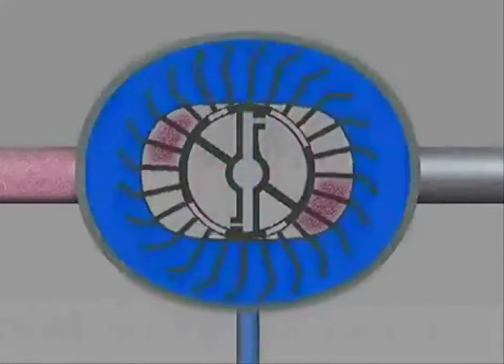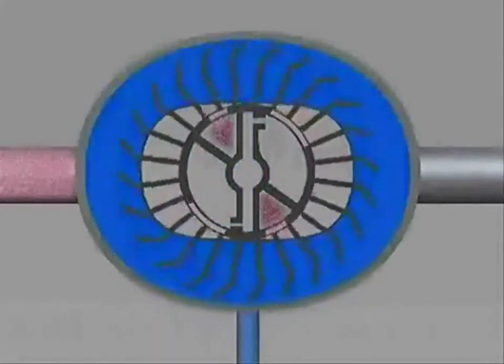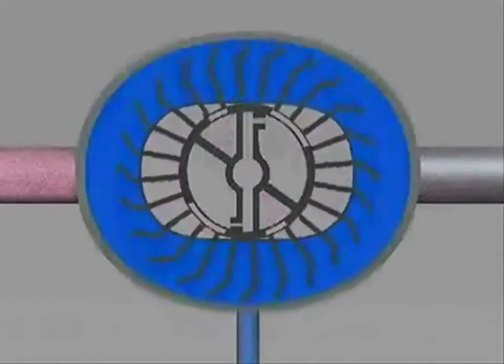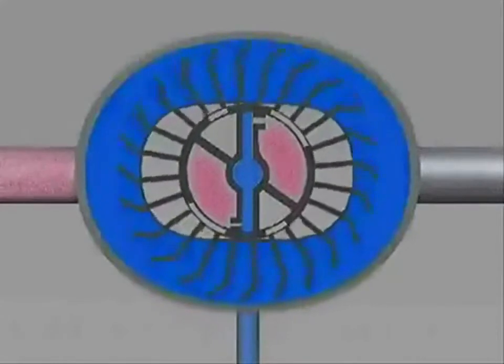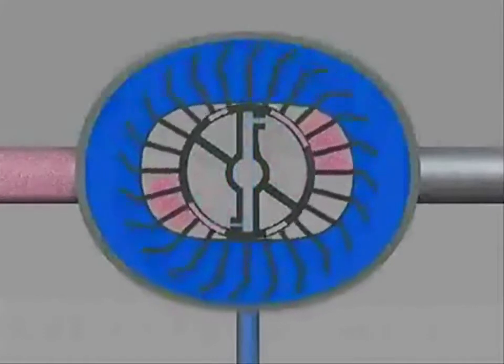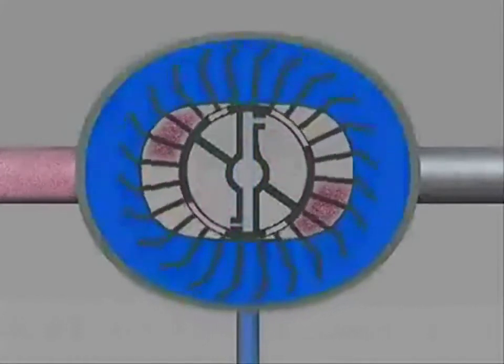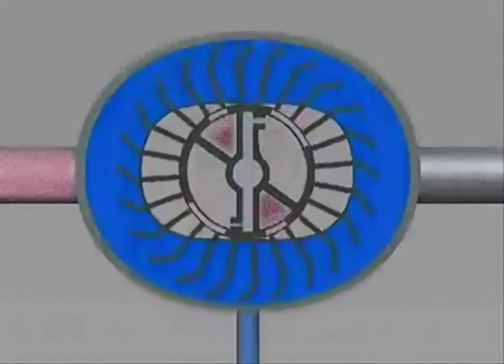During a 180-degree rotation, due to the different section and angular position of the cone opening, the gas undergoes a decrease in volume while increasing its pressure. Near the discharge port, part of the liquid is carried with the gas and conveyed towards the discharge port.